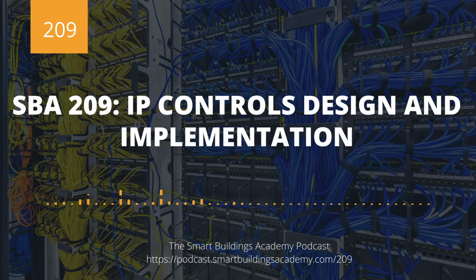But before we do that, I think it's good for us to realize how they are different from regular controllers. So they're very similar in that they have the free programmable interface, they have inputs and outputs. Some of them have the capability to have field trunks coming off of them to connect to other controllers, but they're different than regular controllers in that they, for one, are IP enabled. So they use the internet protocol either through Ethernet cables or through wireless. They also have supervisory device functions for most of them in the actual controller themselves.